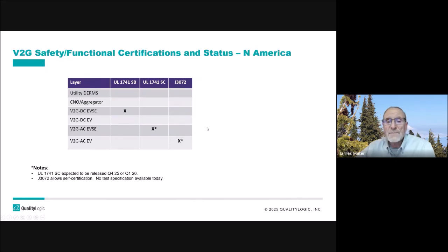Then you've got some safety functional standards that only apply at the EVSE and at the device level. You can see where 1741 SB applies just to the DC EVSE, and the new one, 1741 SC, which we expect to be published later this year, only applies at the EVSE itself, the charging station. And then J3072 is a functional and communication certification for the EV itself.